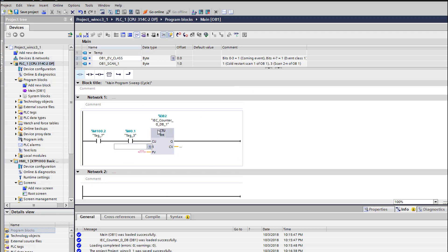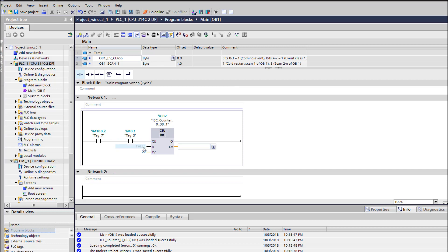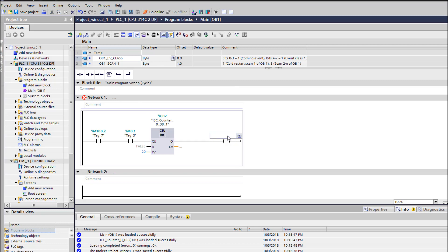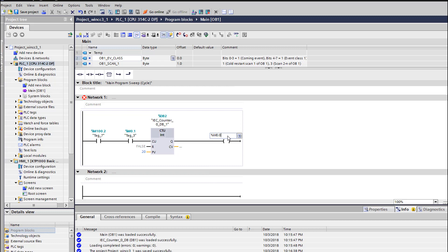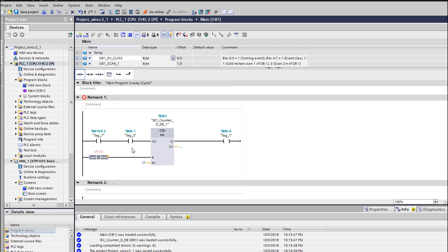If we want to restart it again, we will use this time this PV and this Q, for which value we want Q to be activated. It will be the 20. So once it will reach 20 the Q will be activated which will activate 0.0. Then the same output here will be as an input here. So once this will reach 20 it will be activated which will reset this counter.